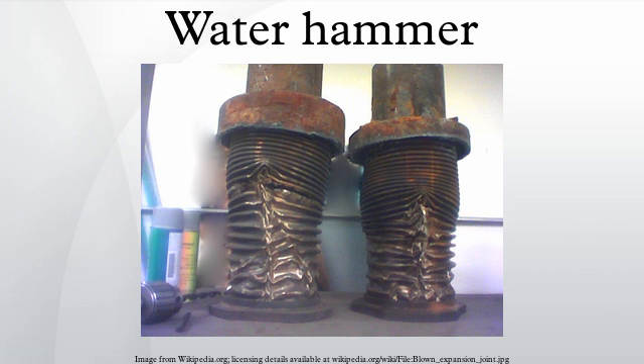Dynamic equations. The water hammer effect can be simulated by solving the following partial differential equations. Where V is the fluid velocity inside the pipe, rho is the fluid density and K is the equivalent bulk modulus, F is the friction factor. Column separation.